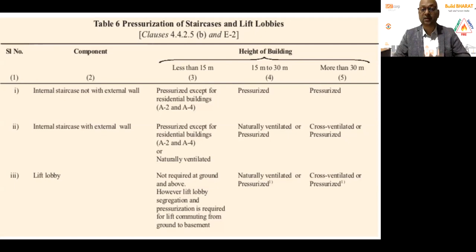No residential area has been classified here as a high-rise building specifically in terms of pressurization, but as an engineer, if you have a residential building more than 30 meters, how do you apply this logic? You can't use the loophole that residential buildings are an exception - smoke and fire can still happen there. So how do you use these techniques? It's the engineer's choice, and it's part of your fire strategy. NBC doesn't look at extraordinary buildings, but generically, on paper, this is the guideline followed.